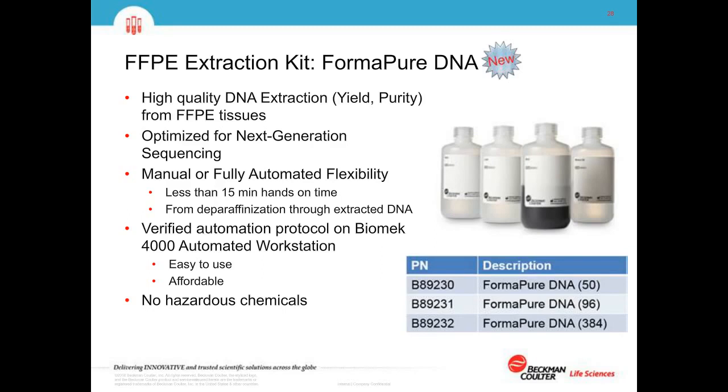Question two: If I wanted to evaluate FormaPure DNA chemistry, who should I contact? If you're interested in evaluating, you can click yes on the poll and someone from Beckman will contact you. In the future, you can contact your local Beckman sales rep or go through the website. Question three: Can you expand on the automated method timing? For a 96-sample processing time on the Biomek FXP, we're looking at about five and a half hours. A lot of that time is incubation time, which automation can't speed up much. For 24 samples, that's approximately four hours and 45 minutes of machine time. The FXP takes advantage of being a dual-pod liquid handler — using the multi-channel pod for full plate transfers while the span pod handles reagent aliquoting for wash buffers, making the most efficient use of kits and time.